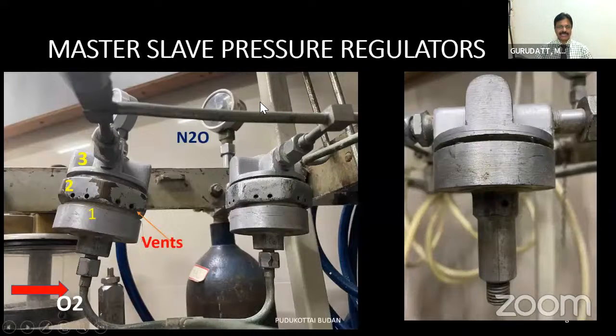Now, coming to the master-slave pressure regulator that I was talking to you about. In Boyle's Mark III and also in the Boyle's Basic, these master and slave pressure regulators were introduced. I was talking to you about the nitrous oxide pressure regulator having 3 chambers: the first chamber, second chamber, and third chamber. You can see the oxygen connection to the first chamber. From the third chamber, the nitrous oxide has to get released. It is only because of the oxygen pressure being applied in the first chamber that the nitrous oxide can flow out. If there is no oxygen pressure in the first chamber, the nitrous oxide is just cut off and cannot flow out. So the nitrous oxide pressure regulator acts as a slave regulator to the oxygen pressure. That's why oxygen is the master and the nitrous oxide pressure regulator is the slave.